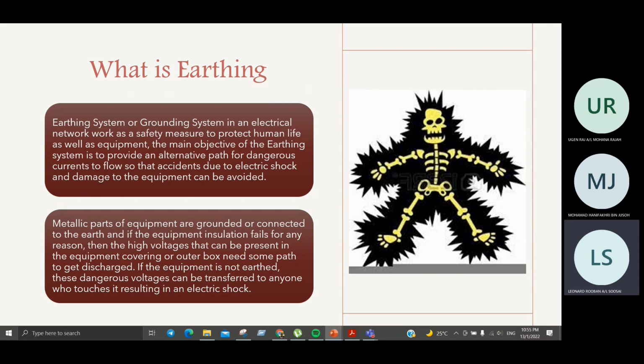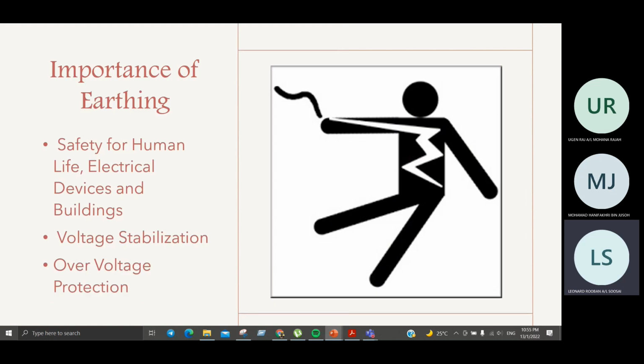Besides that, metallic parts of equipment are grounded or connected to the earth, and if the equipment insulation fails for any reason, then the high voltages that can be present in the equipment covering or outer box need some path to be discharged. So if the equipment is not earthed, these dangerous voltages can be transferred to anyone who touches it, resulting in an electrical shock, which may cause serious injury or even death. So these are the importance of earthing. The first is safety for human life, electrical devices and buildings.